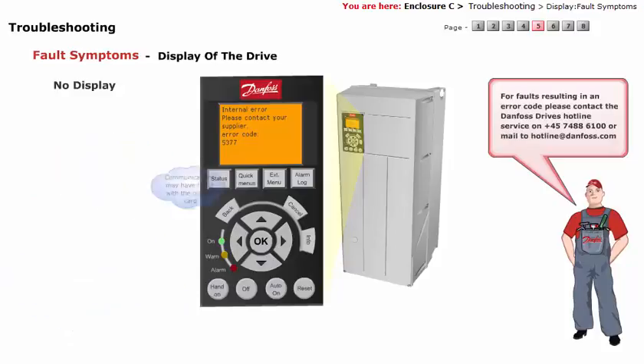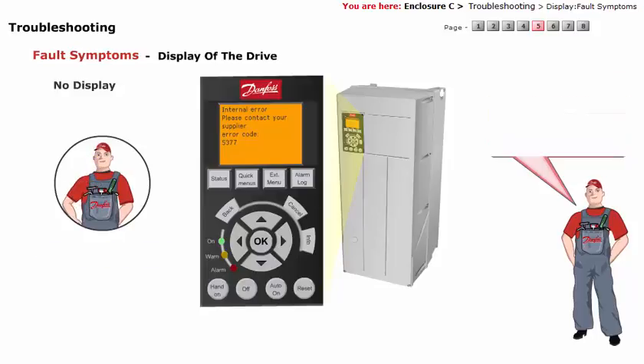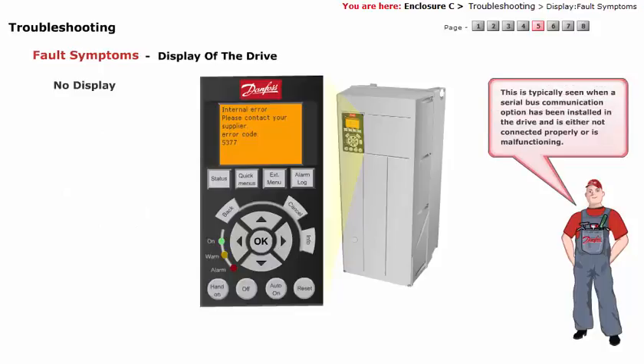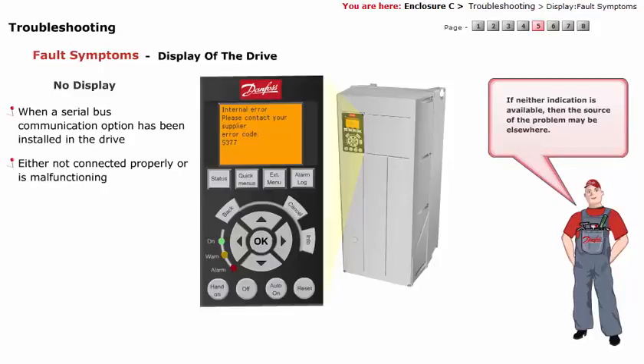An error code exists in the FC automation drive which indicates that communications may have failed with the control card. For faults resulting in an error code, please contact the Danfoss drives hotline service on 457488 6100 or mail to hotline@danfoss.com. This is typically seen when a serial bus communication option has been installed in the drive and is either not connected properly or is malfunctioning. If neither indication is available, then the source of the problem may be elsewhere.